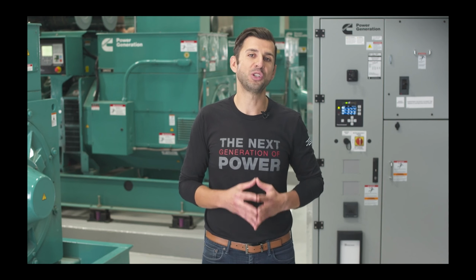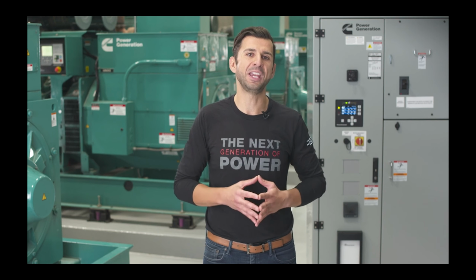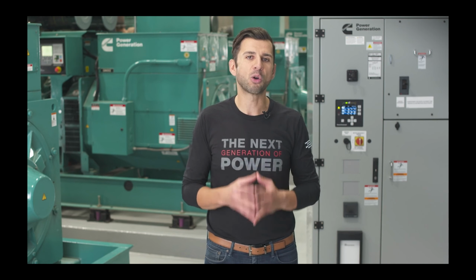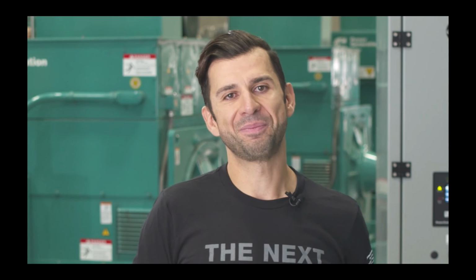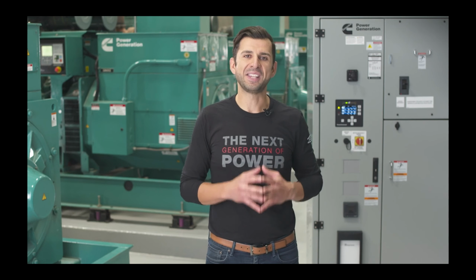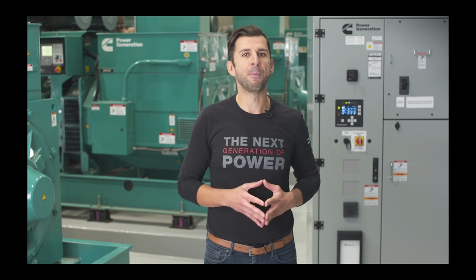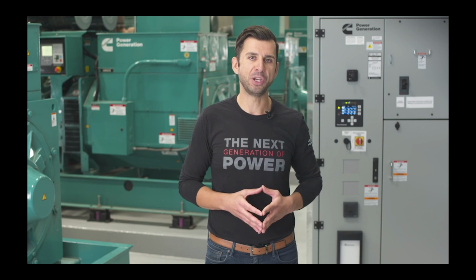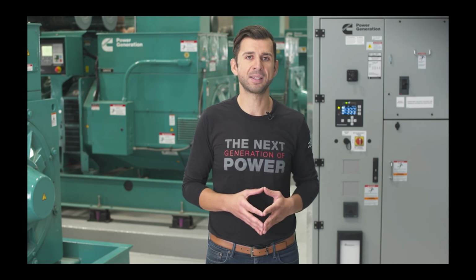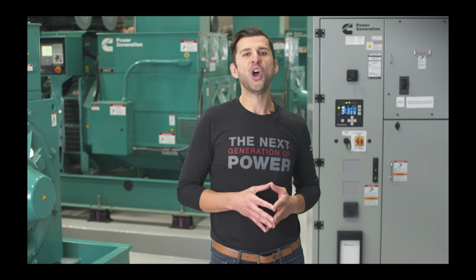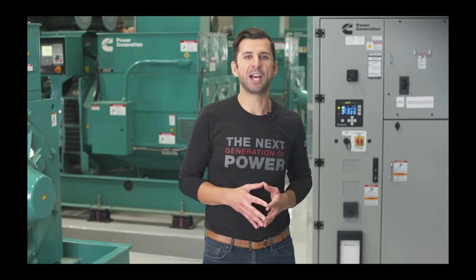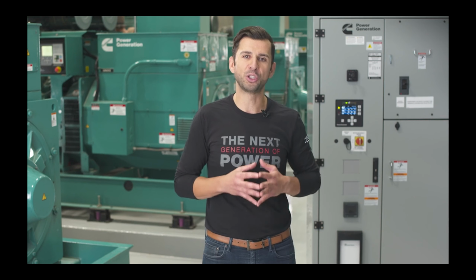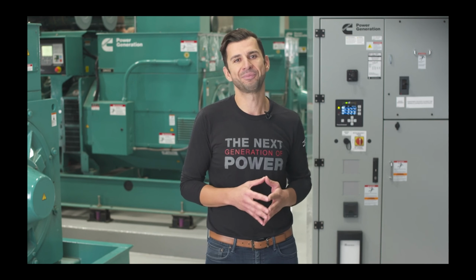What's more, the transfer switch control has been designed to interface with the same Cummins service tool that is used across Cummins power generation products, including transfer switches, switchgear, digital master controls, and generator sets, for a completely integrated power system. With all control modules having the same layout and structure in the service tool, combined with a common set of fault codes, operation and troubleshooting of equipment is less complex for operators and technicians. All you need is one technician with one laptop and a single software to easily set up or troubleshoot multiple components in the power system.